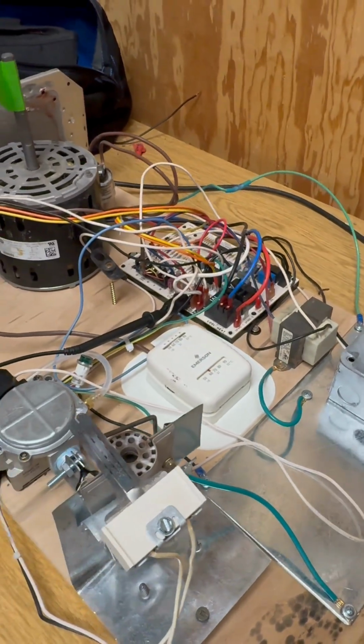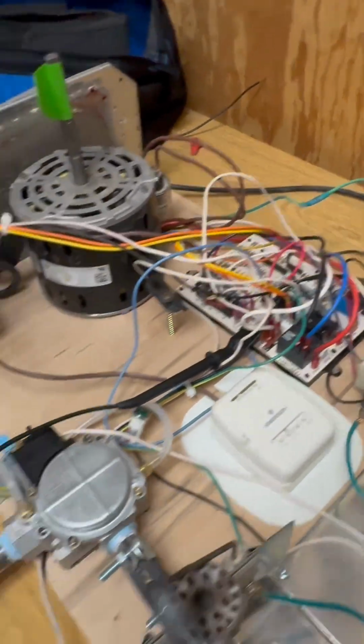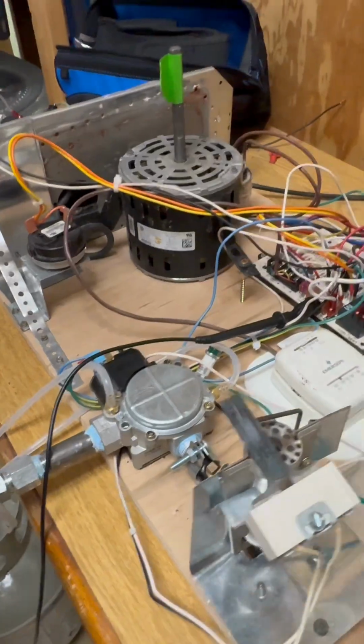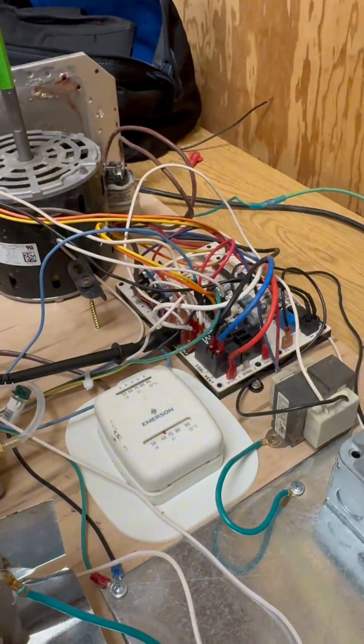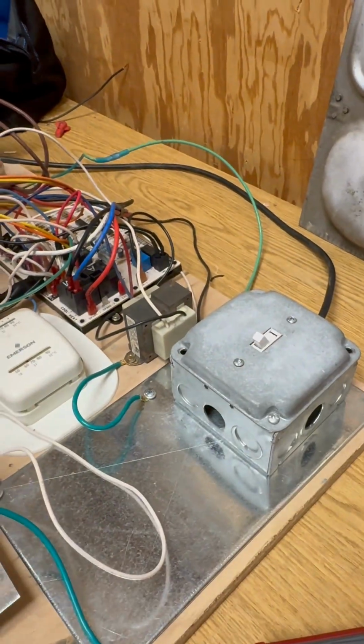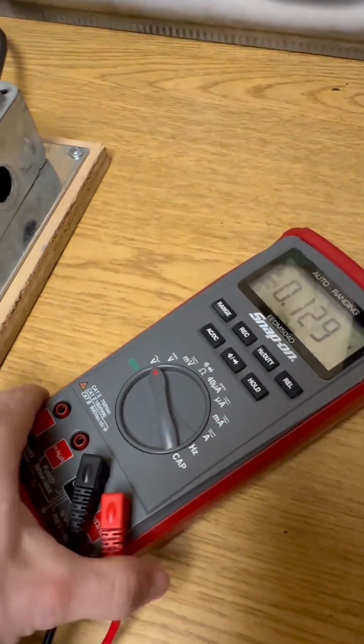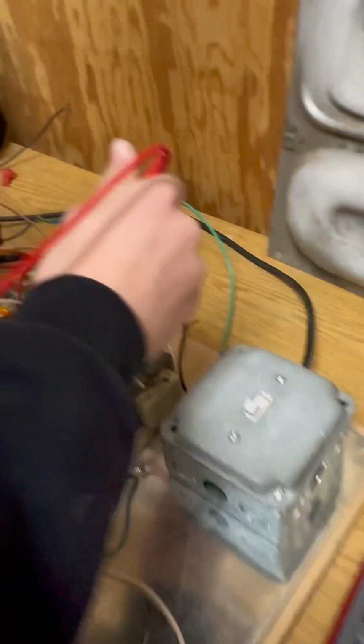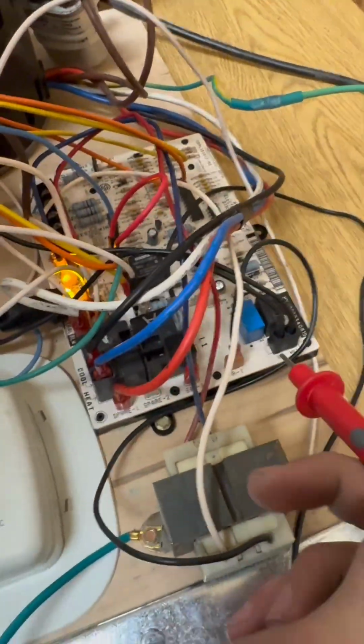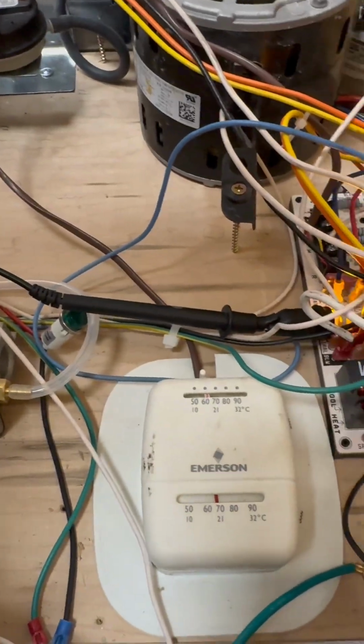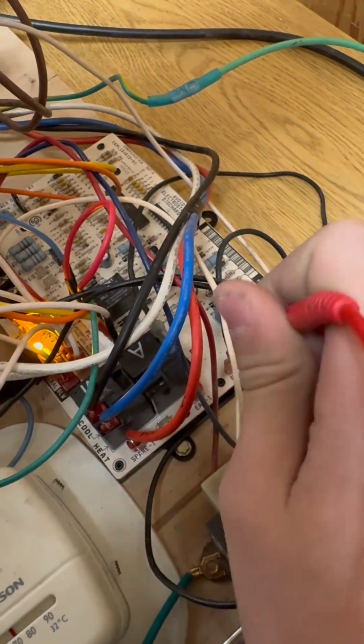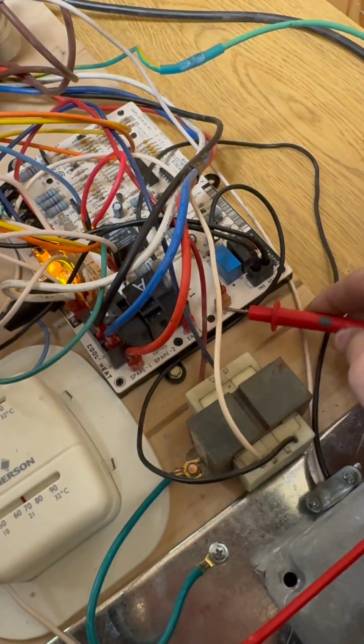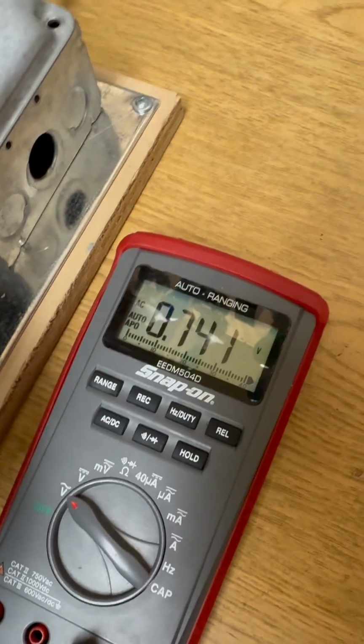Today we're going to be showing you how to diagnose a bad furnace board and to make sure your gas valve is opening properly. First off, we're going to check to ensure that we have power to our furnace board. Always get a meter out. Yep. So I have our ground for our meter hooked up to our neutral bus, and I'm going to our line side with our positive meter probe.